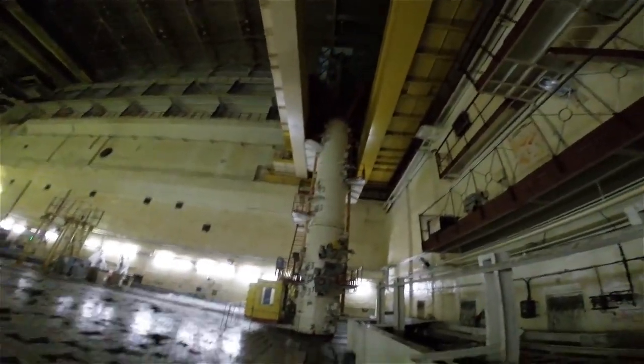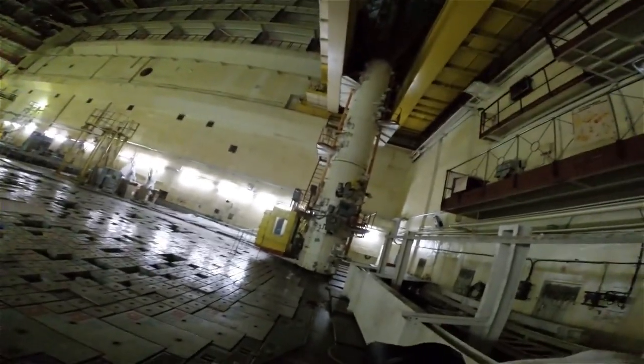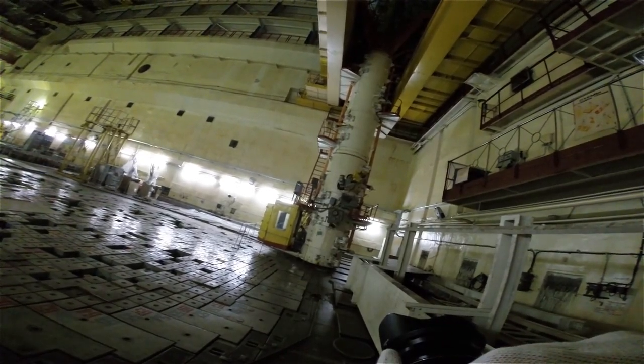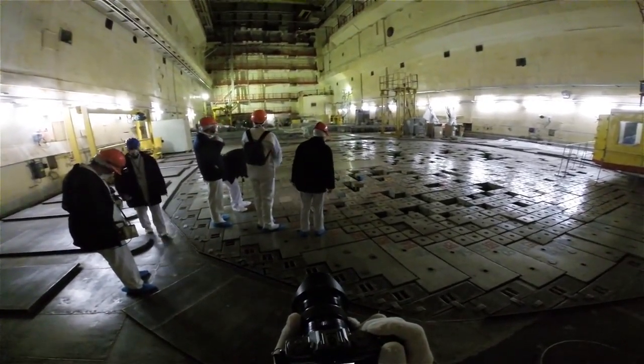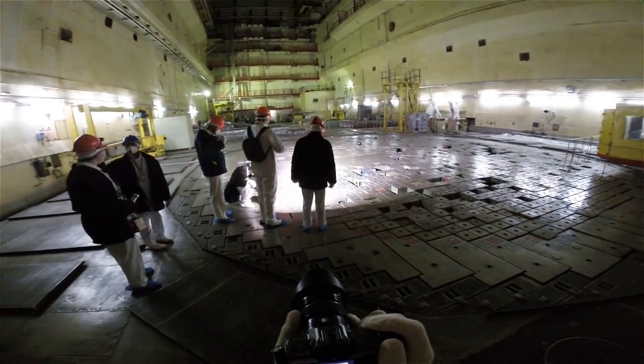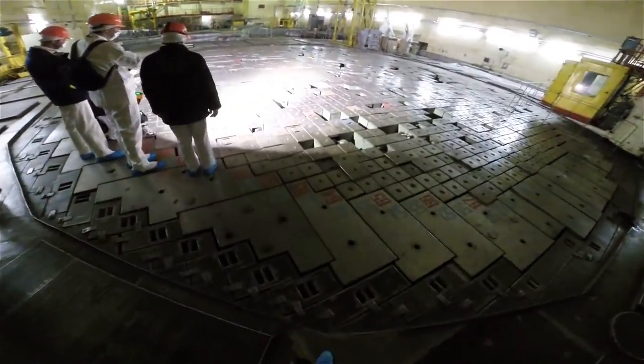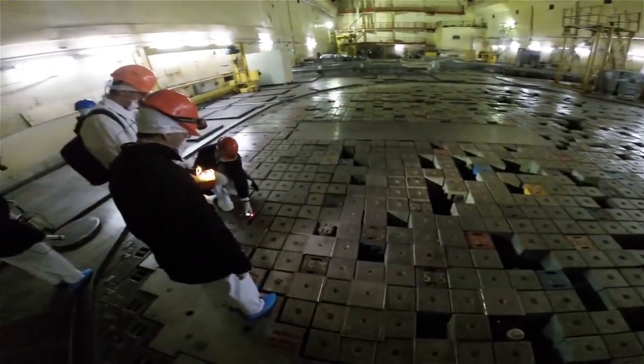Look at that fuel handling machine. The RBMK reactor is constructed from graphite blocks that are penetrated vertically by pressurized tubes carrying nuclear fuel and other in-core devices like control rods. What we're looking at here is the top plate of the reactor where it's been penetrated by all of these channels, with a protective heavy metal cap over each one, also protecting from mechanical damage.